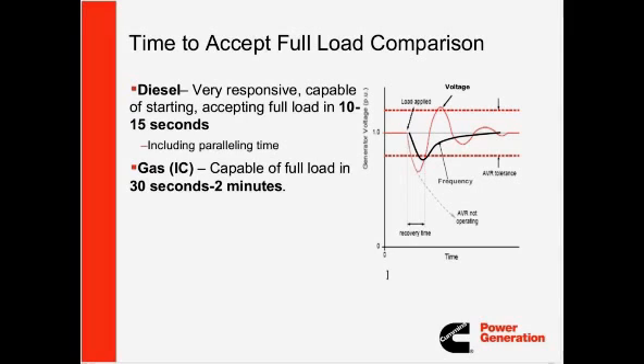The problem with gas gensets is that it may take up to 2 minutes in some cases to recover to nominal frequency and voltage, and it may not be able to accept full load. There are improvements now in natural gas, and it used to take about 1 to 2 minutes to get there, but now we are seeing improvements as they can start and accept the load and recover to nominal frequency and voltage within 30 seconds, but it's still much higher and worse than diesel generators. This makes diesel generators the preferable choice for standby and emergency applications.